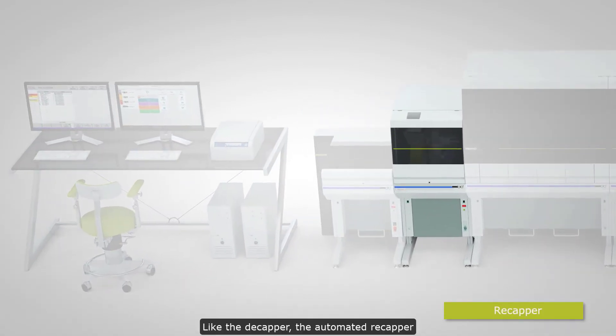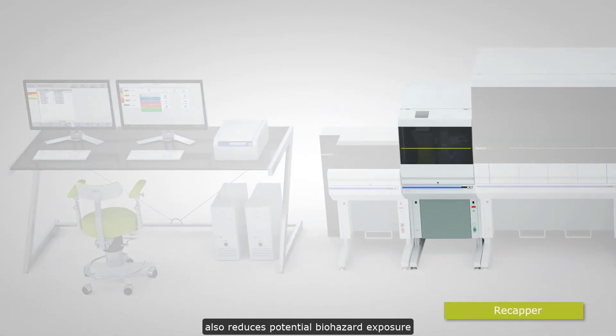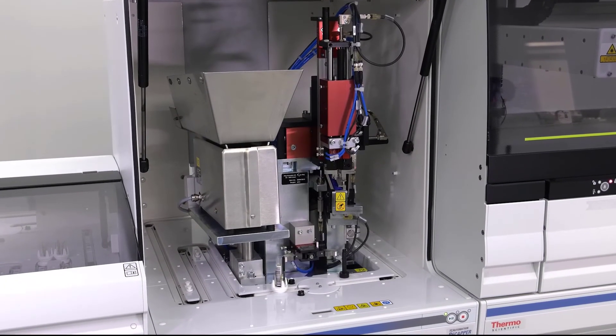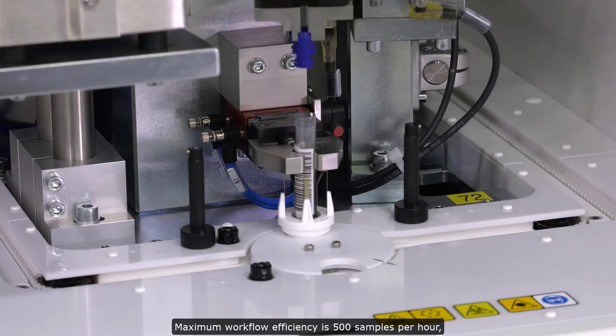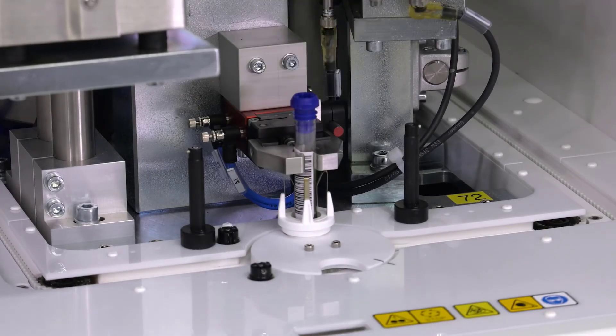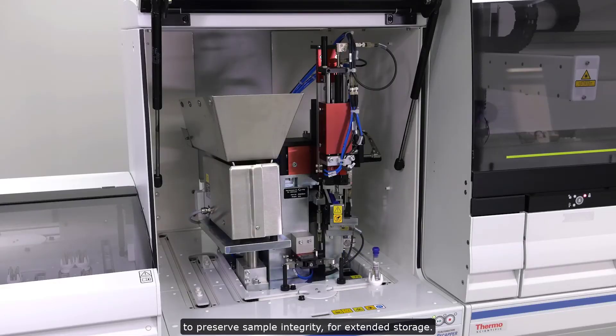Like the decapper, the automated recapper also reduces potential biohazard exposure and reduces repetitive motion, mitigating risk to laboratory personnel. Maximum workflow efficiency is 500 samples per hour, using a manufacturer-approved cap to preserve sample integrity for extended storage.